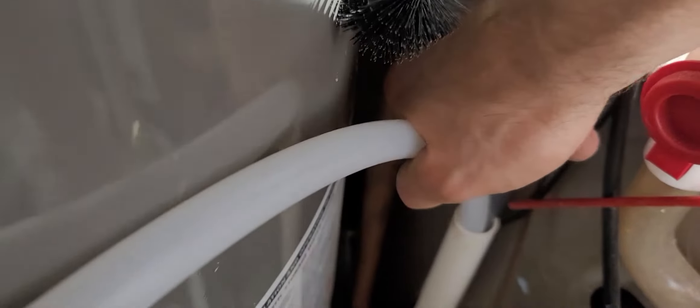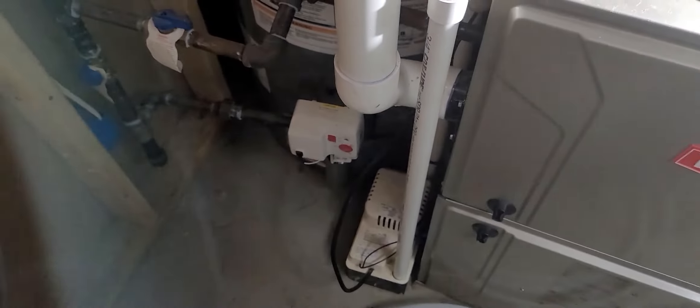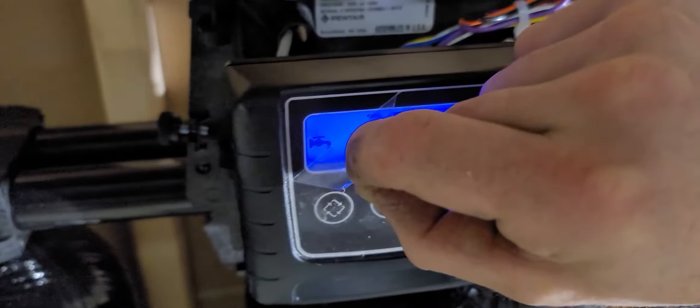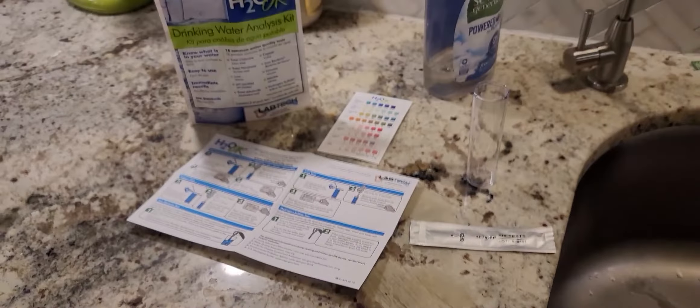Here I'm installing 3/4 inch drain tubing. This needs to go into a sink or a drain pipe. I thought I was going to be smart, and I actually plumbed it to this water pump I had sitting next to me at my boiler. This takes care of the excess water for the humidifier. But as I learned very quickly, it cannot pump nearly fast enough for that drain. That drain is basically nearly city pressure. But more on that later.